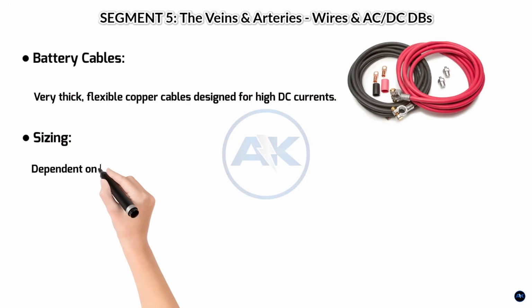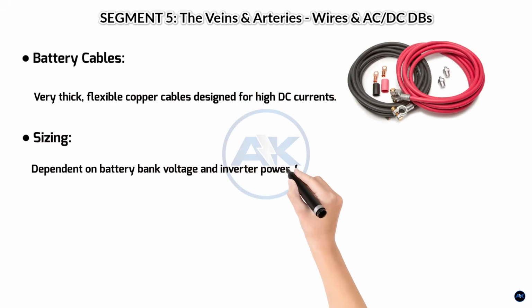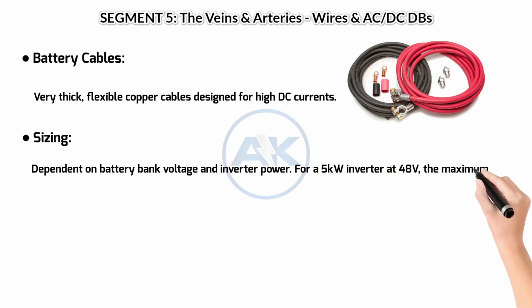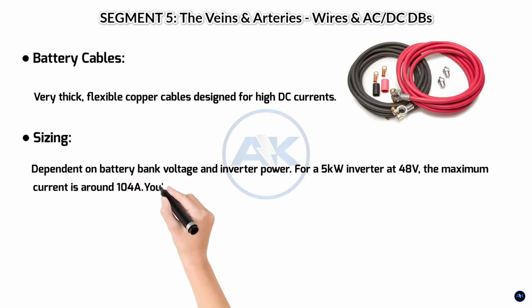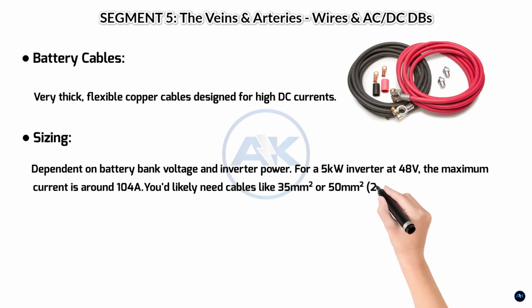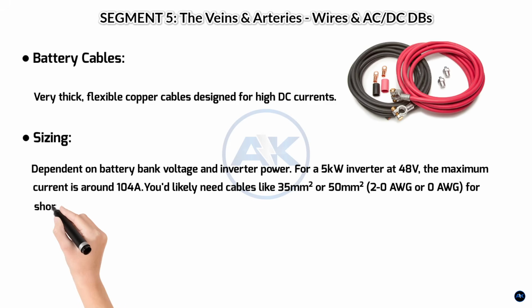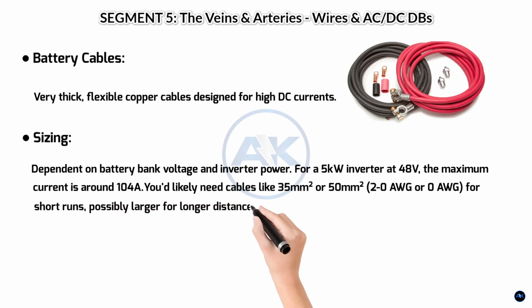Sizing: dependent on battery bank voltage and inverter power. For a 5 kilowatt inverter at 48 volts, the maximum current is around 104 amps. You'd likely need cables like 35 mm squared or 50 mm squared, 2 American wire gauge or 0 American wire gauge for short runs, possibly larger for longer distances.